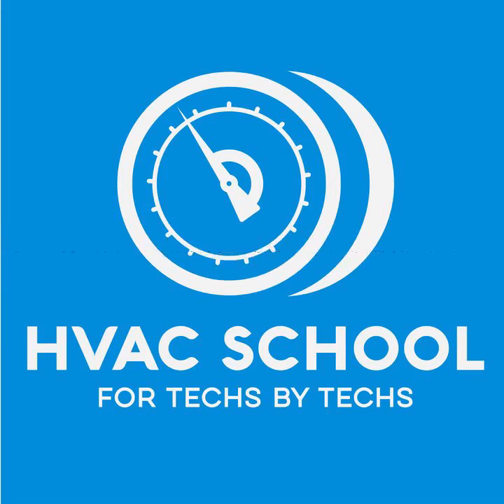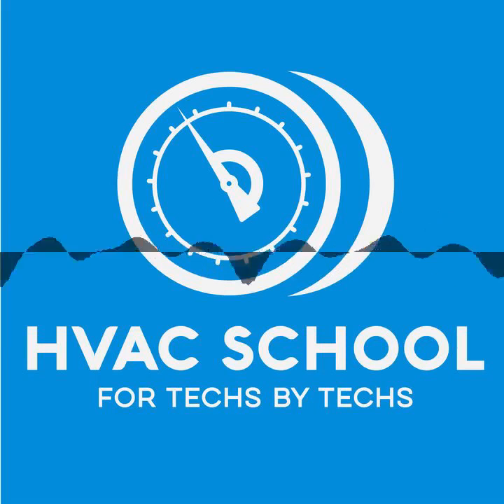So, you're down in the Florida area where dehumidification is key. Yes, you have high ambient temperatures, such as high dry bulb temperatures, but at the same time, along with those, you have high moisture levels, high relative humidity. And RH is, as it says, relative humidity. And as we talked about on our earlier podcast dealing with humidity, how much moisture the air holds is relative to its temperature. So on a 90 or 95 degree day, the air can hold so much moisture that the latent heat of the air is off the scale. You can't even plot it on a standard psychrometric chart unless you use a high temperature version of one because the energy levels are just too high. So what do you do? Well, you set up your airflow at, say, 350 or 320 CFM a ton. You drop your evaporator temperature and you have a highly latent focused process. Unfortunately, this is a necessity because it is not efficient.